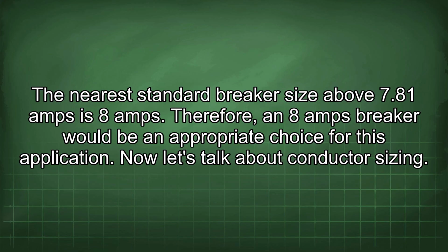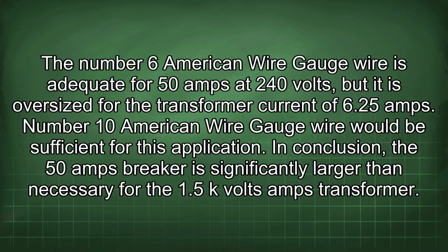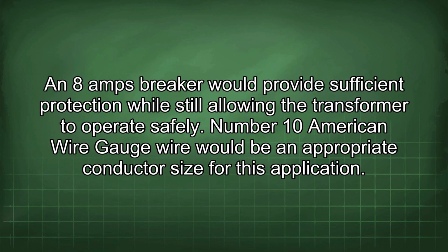Now let's talk about conductor sizing. The number 6 American wire gauge wire is adequate for 50 amps at 240 volts, but it is oversized for the transformer current of 6.25 amps. Number 10 American wire gauge wire would be sufficient for this application. In conclusion, the 50 amps breaker is significantly larger than necessary for the 1.5 kVA transformer. An 8 amps breaker would provide sufficient protection while still allowing the transformer to operate safely. Number 10 American wire gauge wire would be an appropriate conductor size for this application.